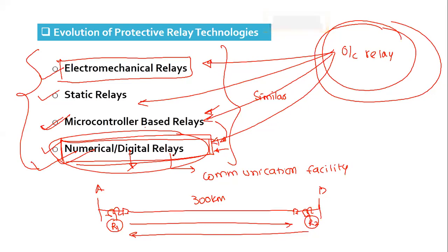Adaptive characteristic means depending upon the situation, you are going to change the characteristic of the relay as per the program. So this has multifunctionality, and nowadays this is the widely used relay in the field. It can perform multiple functions. The same relay can offer you 10, 20, 50, 100, whatever number of protections you require. Only one single relay is enough for all the functions.